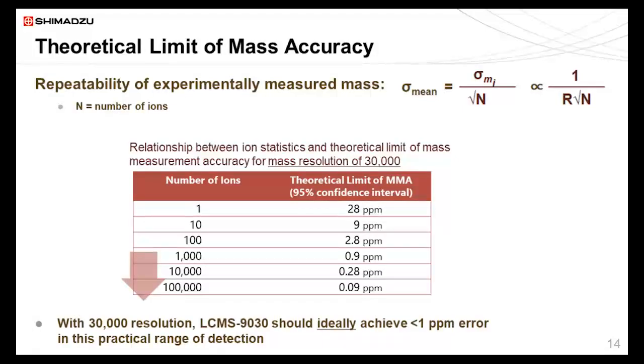So what I'm trying to say here is that it's not just the resolution, but also sensitivity, or the number of ions being sampled in a single measurement, is an important factor for getting good mass accuracy. And mathematically, this can be represented as shown. Theoretical limit of mass accuracy can be shown by calculating the repeatability of experimentally measured mass, such that the standard deviation of this measurement is the standard deviation of the individual ion measurement, which is dictated by resolution, divided by the root of the number of ions being sampled. And this is proportional to 1 over R root n, with n being the number of ions being sampled.